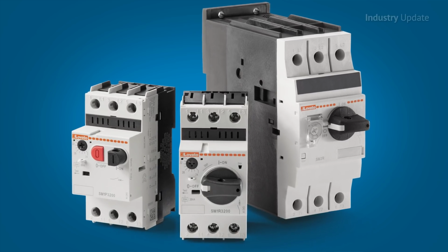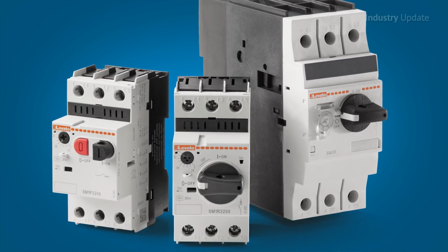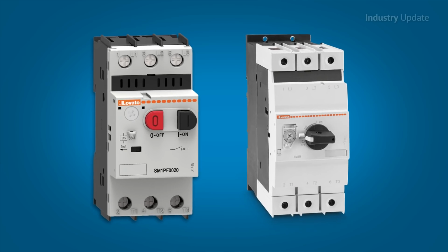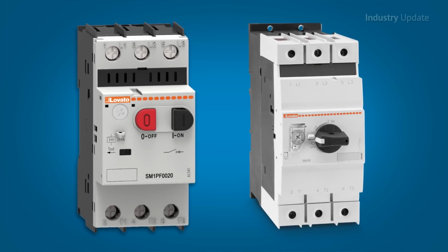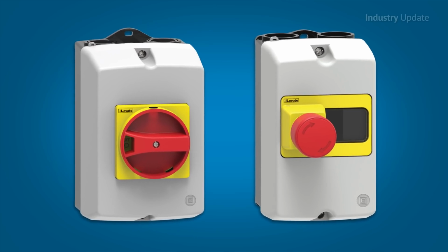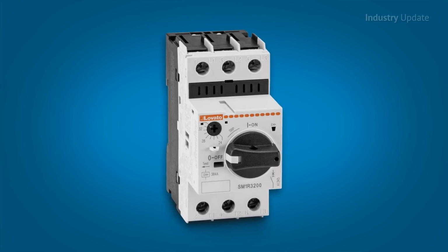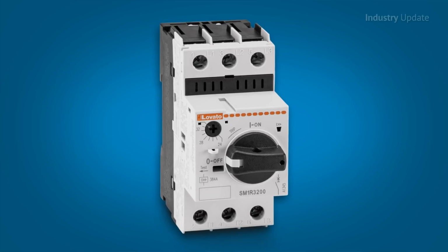Available throughout Australia from Mechtric, these circuit breakers are available with either push-button or rotary knob actuation, and both types can be padlocked in the off position for extra safety during maintenance. Both thermal and magnetic trip versions are available with ratings from 100 milliamps to 100 amps and a high breaking capacity of up to 100 kiloamps.